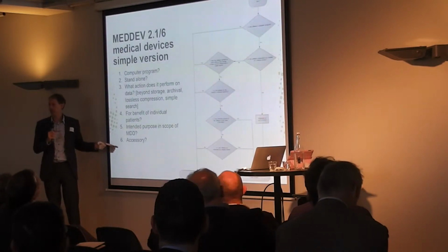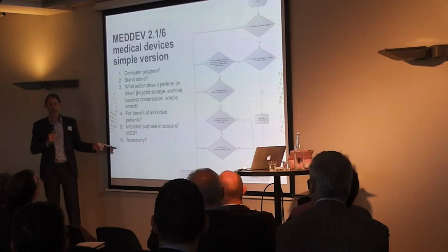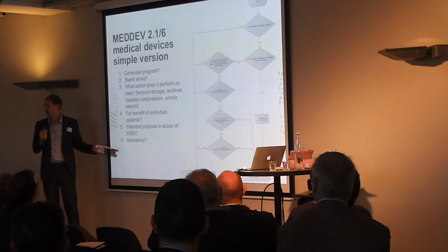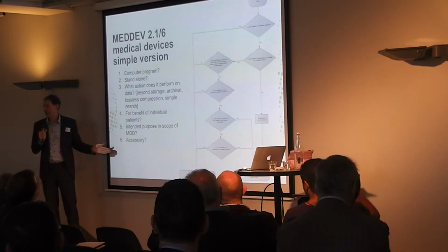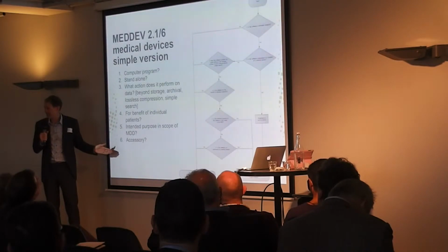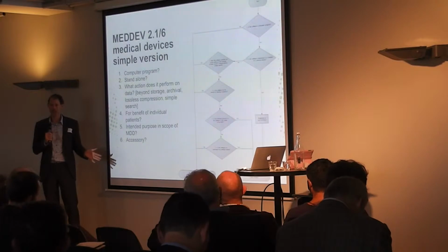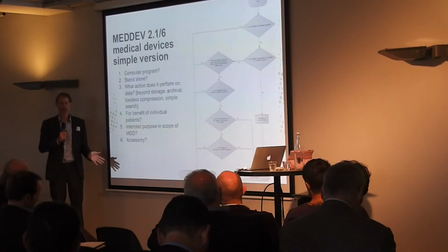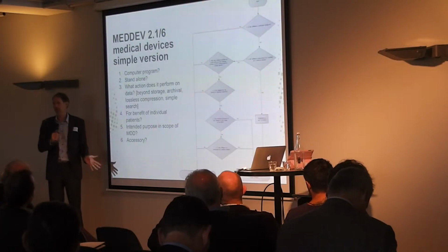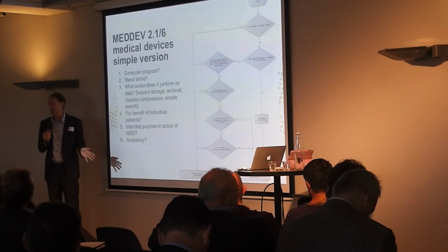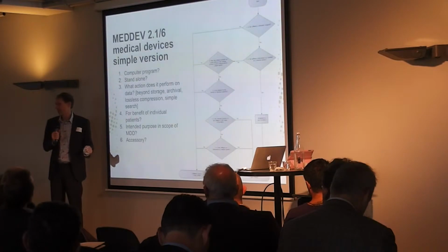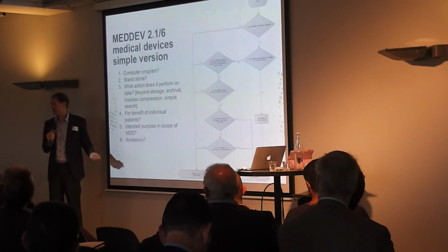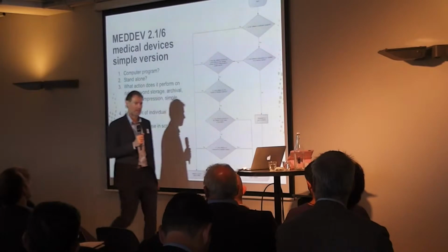And accessory, I point this out because the medical devices regulation proposes to include a definition of accessory that is much wider than the current definition, because the current definition is an accessory is anything that enables a medical device to achieve its intended purpose. The new definition is enable or assist. Well, what's assist? That can be really broad. So good luck with that.